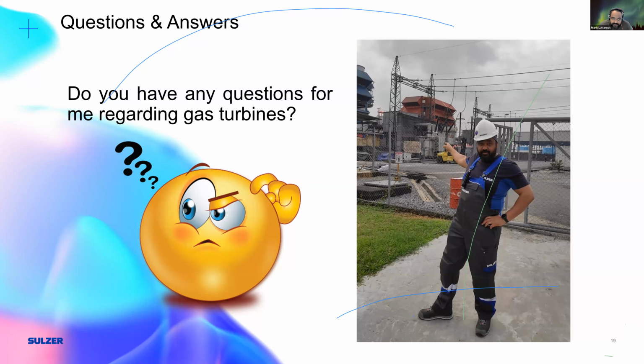Not at all. Some of them just have a bird screen in front - they don't even have filters installed. In winter, if they need to run, they have to have glycol going through pipes to make sure no ice forms, because ice going through the compressor would damage it. These systems are so old that apart from a bird screen there's really nothing in there, so every time there's an outage we manually have to clean the IGVs because they get very dirty.